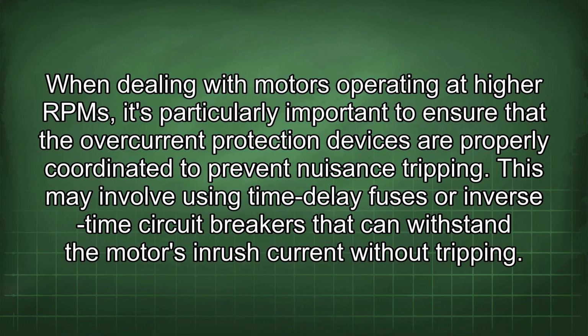When dealing with motors operating at higher RPM, it's particularly important to ensure that the overcurrent protection devices are properly coordinated to prevent nuisance tripping. This may involve using time delay fuses or inverse time circuit breakers that can withstand the motor's inrush current without tripping.